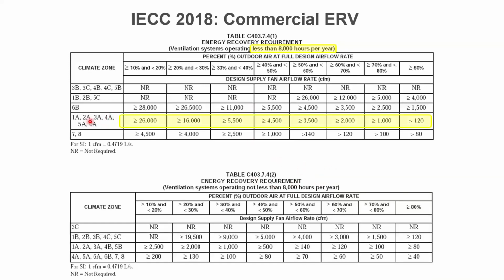So if I look at climate zone 5A or 6A, that's this yellow bar across here. If I have 70% outside air, which is a pretty large amount, and my supply fan is 1,000 CFM or larger, right? So that means I have 700 CFM of outside air, then I have to do an ERV. If I look over here at 30% outside air, on a system that has a total of 5,500 supply air, got to have an ERV. And if I'm down here in the really small range with only 10 to 20% outside air, then I have to have a pretty large air handler to require an ERV.